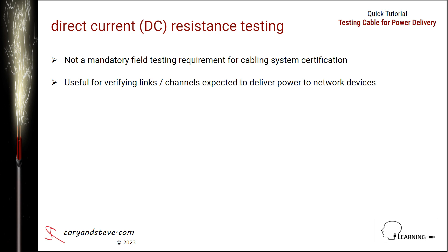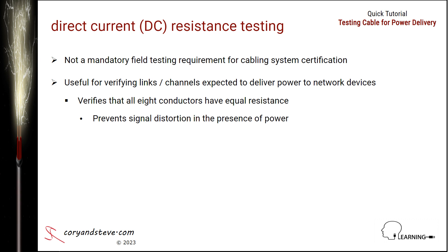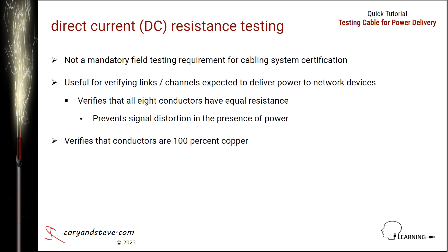DC resistance testing verifies that the eight conductors that make up the four twisted pairs in a cable have an equal or nearly equal amount of resistance. An excessive difference between the DC resistance values of the two conductors in any pair, or between any of the four pairs, can result in communication delays or link failure due to data corruption caused by signal distortions. As an added bonus, this type of testing will also verify the metallic composition of the conductors and identify any non-code-compliant or counterfeit cable construction, such as copper-coated aluminum cables advertised as 100% copper.